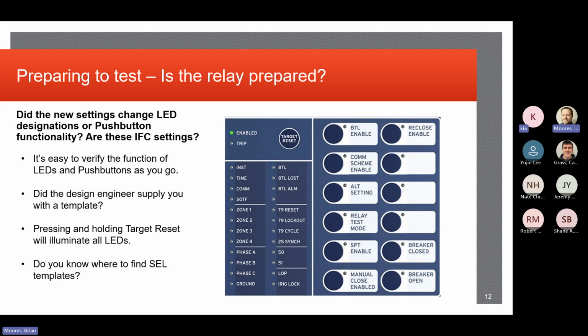So we do that end-to-end testing, and we've got communication channels and some latencies and all that stuff. We want to make sure we validate that information. So that's where the SER, from a testing perspective, gets very important. And in the case and scenario like you just mentioned, one relay had a trip, one maybe didn't trip, we would look at that, next relay out to see if it saw it, if it was in a direction behind it, or if it was somewhere else. So it becomes very important.